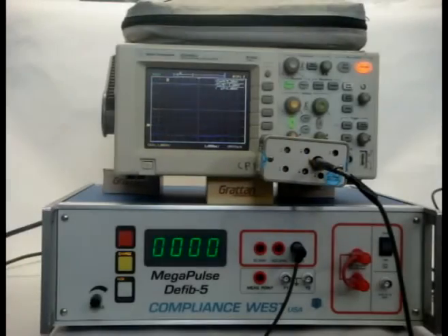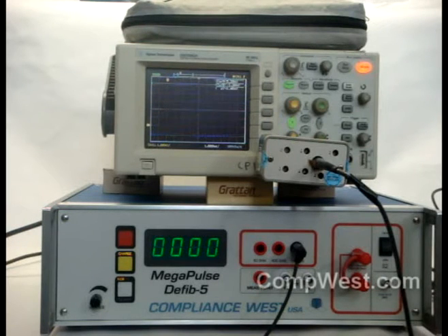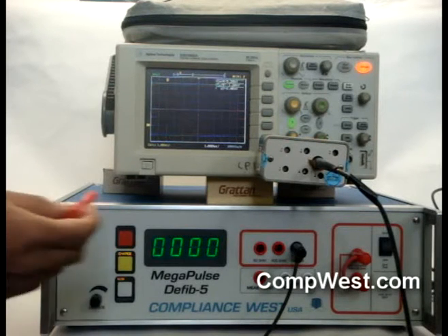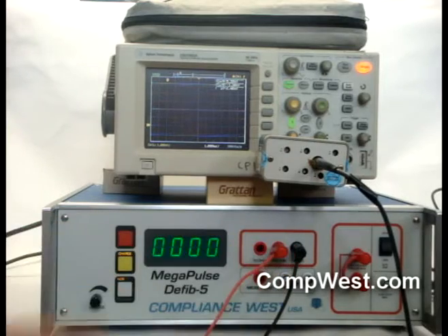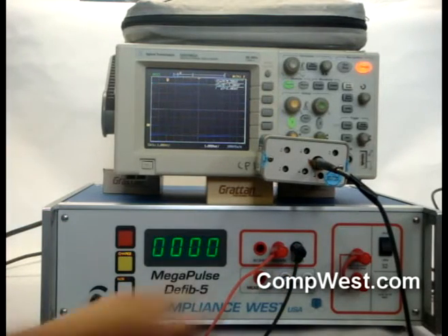This video will talk about IEC 60601 energy determination with the Defib-5 using the Excel method. IEC 60601-1, Issue 3, Paragraph 8.5.5.2 outlines the procedure to conduct the energy reduction test to test the delivered defibrillation energy when the device under test is also connected. To run this test, the Defib-5 is configured to deliver a 5,000 volt pulse through the 400 ohm load using the 25 millihenry choke.